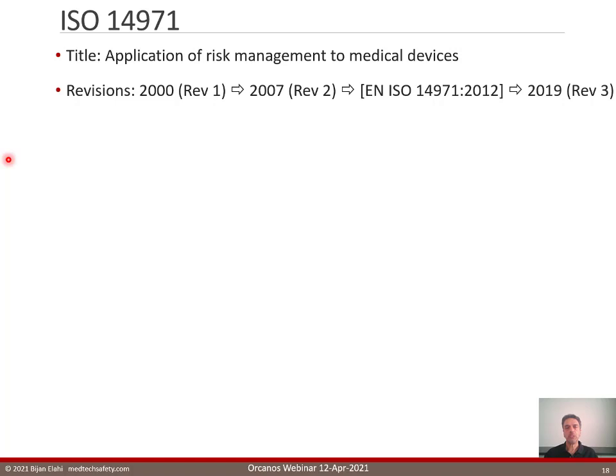The first revision of ISO 14971 was released in year 2000. In year 2007, revision 2 was released, which removed and canceled revision 1. In 2012, the European community decided that the international standard, ISO 14971 2007, was not sufficiently aligned with the Medical Device Directive. So they added 3 annexes, ZA, ZB, and ZC, to it to create the conformity that they wanted. Later on in December of 2019, revision 3 of ISO 14971 was released, and that is currently the state of the art, and it has removed the 2007 revision 2 of ISO 14971.